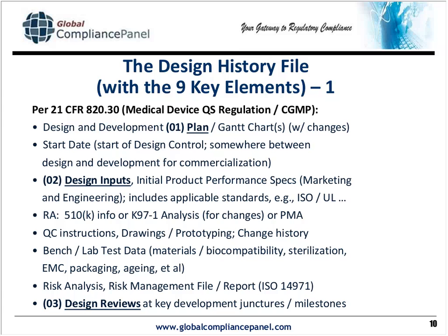QC instructions, drawings, prototyping, SOPs, change history, etc. would be part of your documentation. Part of the many verifications leading to product validation would be bench testing for functional testing, lab test data, for example, maybe on material strength, material biocompatibility issues.